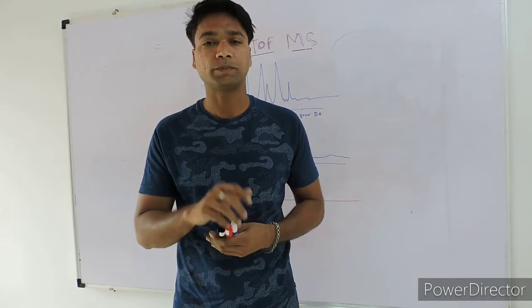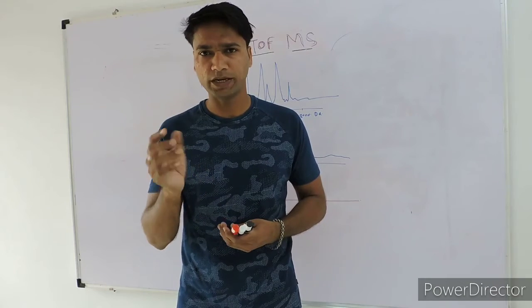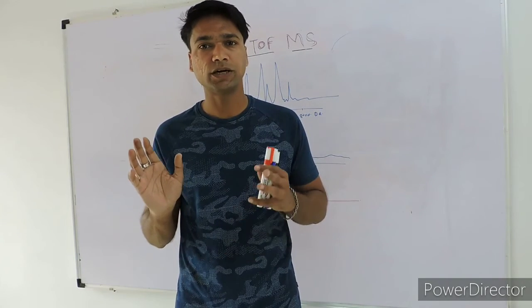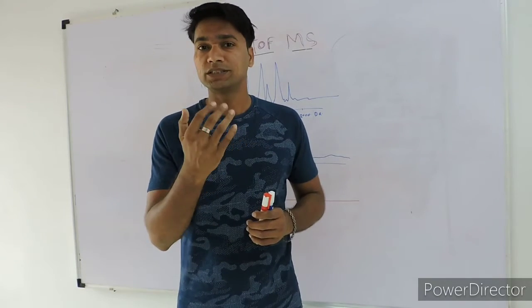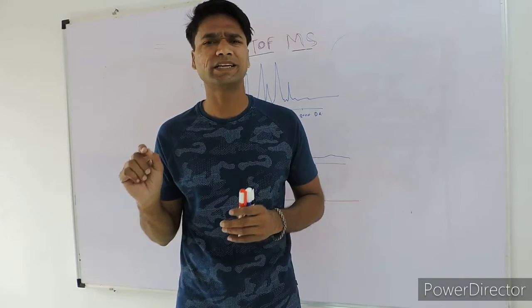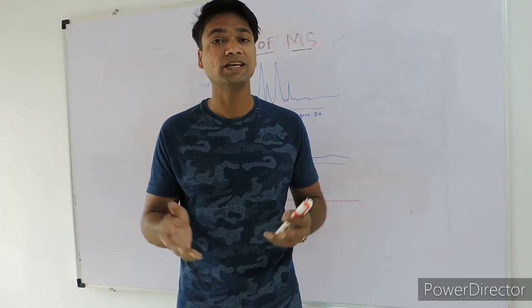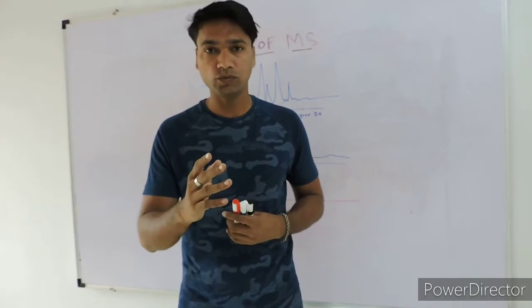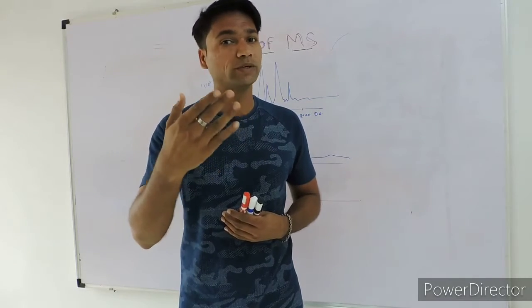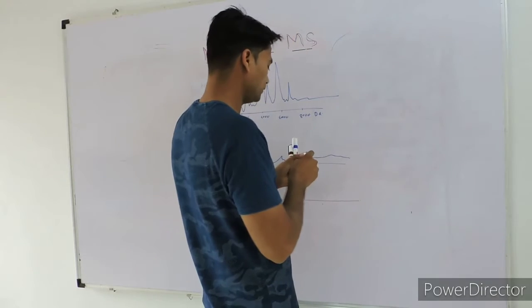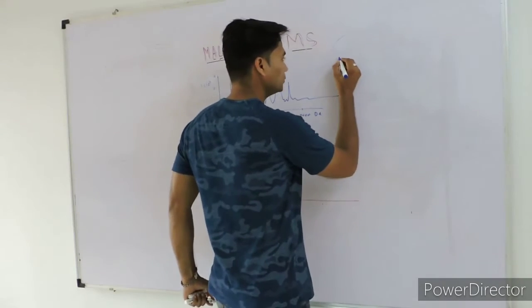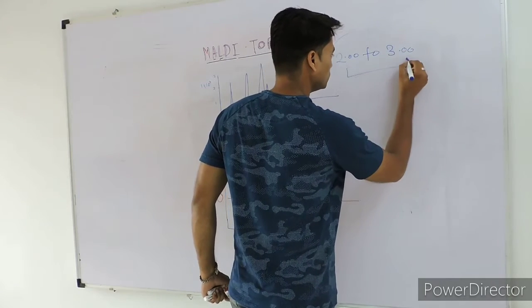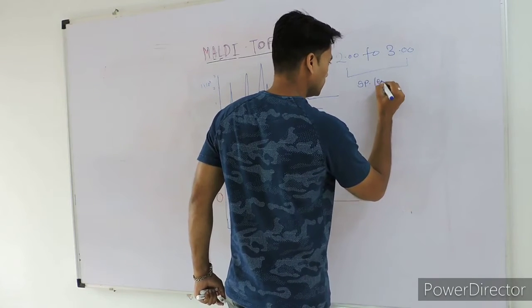Now let's see what kind of spectra results and color codes are related to the MALDI-TOF MS result environment. First is the green color — whenever you see the report and you see the green color code with your identified species, that means your identification is up to 100 percent. Like in DNA sequencing when you BLAST in the database, you get percentage similarity — 99%, 99.5% — the same manner is used here. But here the score value is what matters. If the score value is more than 2, we get this at the species level. So if your organism is showing a score value of 2 to 2.3, that is called species-level confirmation.